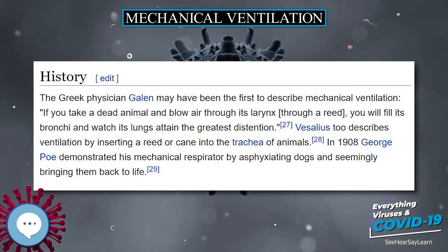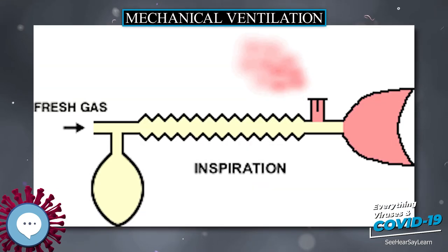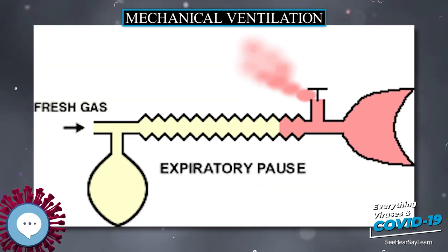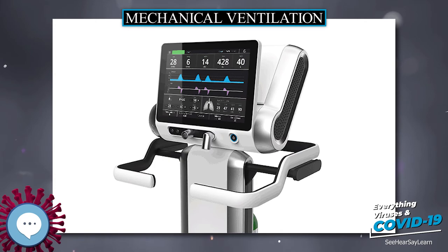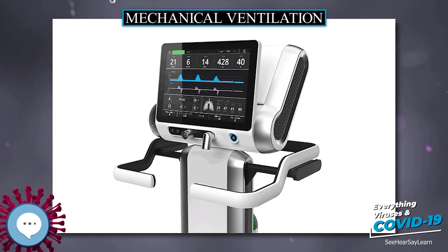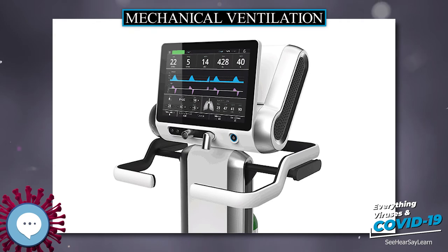Ventilators come in many different styles and methods of giving a breath to sustain life. There are manual ventilators such as bag valve masks and anesthesia bags that require the user to hold the ventilator to the face or to an artificial airway and maintain breaths with their hands. Mechanical ventilators are ventilators not requiring operator effort and are typically computer-controlled or pneumatic-controlled. They typically require power by a battery or a wall outlet, DC or AC, though some ventilators work on a pneumatic system not requiring power.